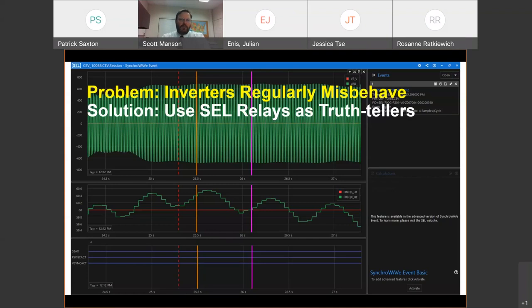Here you see an example of what my teams and I and many engineers throughout the industry use microprocessor devices for. In this case, the relay is the device connected to current sensors and voltage sensors. Therefore, we can measure frequency, we can measure voltage, we can measure current, power. We are a meter, a very high sample rate meter. Also an oscillography recording. Here's an oscillography recording right out of an SEL relay. That's a 700, I think it's a 700G.